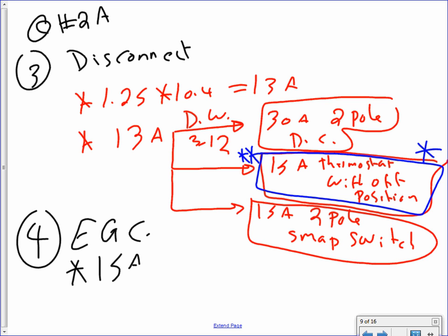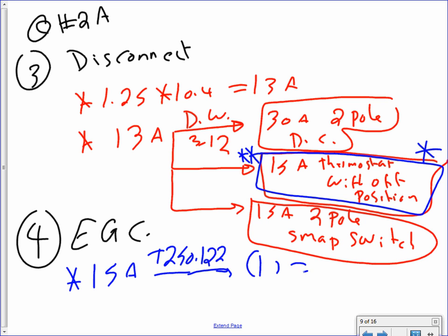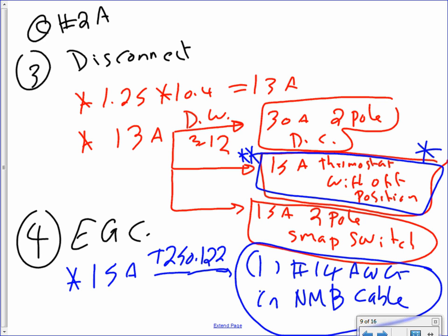The last thing is equipment grounding conductor. For equipment grounding conductor, guys, you take the 15 amp, take it to 240. You take it to Table 250.122. You'll get conductor number 14 AWG in NM-B cable. And typically this will be bare in an NM, bare, no insulation. Typically. Could it be insulated? Bring it on. No problem.